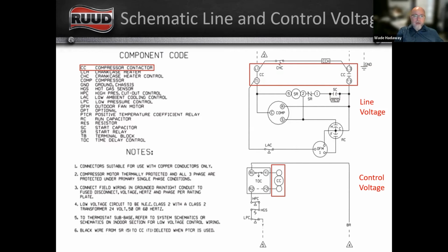And when we look at the pictorial diagram, you'll see that the contactor is just one piece instead of being broken up by voltages, by high voltage or line voltage or control voltage. And then down at the bottom there, 4 and 5, we have got our Y and our common, right? Y would be cooling from indoor, the yellow wire, and then the brown wire would be our common.